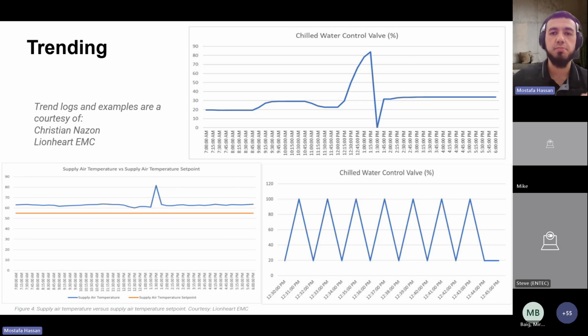So at first glance, these two trends may not pique any interest, right? Chilled water control valve signal appears to be normal, right? Aside from some spikes early afternoon, and that can represent an influx of people coming back from lunch and whatnot, right? The only thing is, a huge focus here is to consider this carefully because we're looking at 15-minute intervals, right? So this spike, the 15-minute intervals are really a snapshot of what's happening. So the temperature spike as well can actually indicate a deeper issue, right?